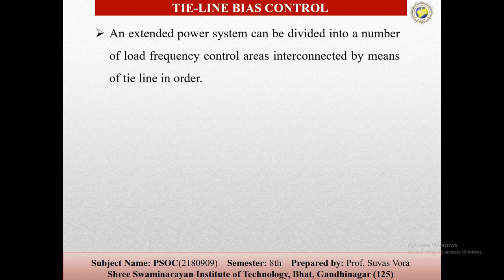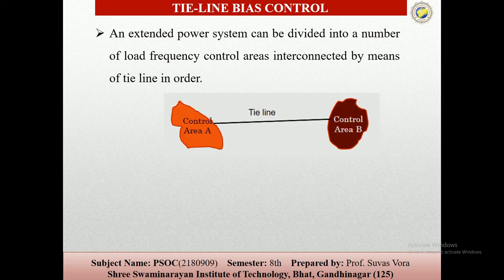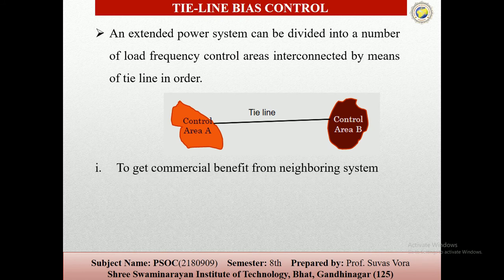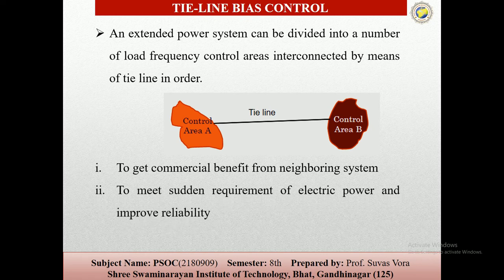In the tie line bias control system, the extended power system can be divided into a number of load frequency control areas interconnected by means of tie lines. So these are the two control areas, control area A and control area B, and these two areas are connected with tie lines. This is to get commercial benefits from the neighboring systems, to meet the sudden requirement of electrical power, and to improve the reliability.